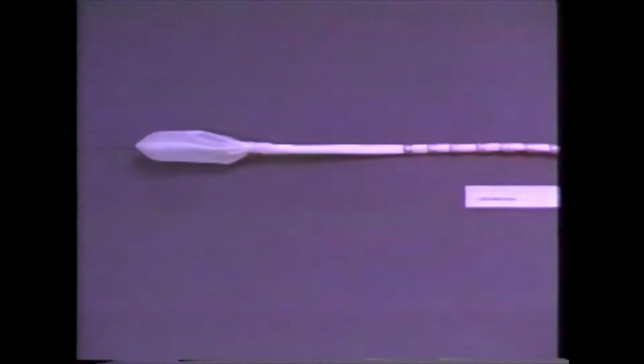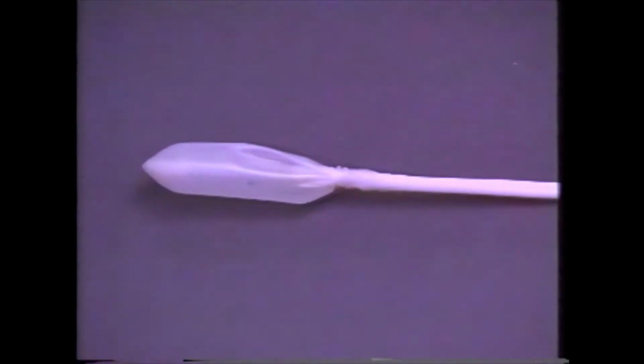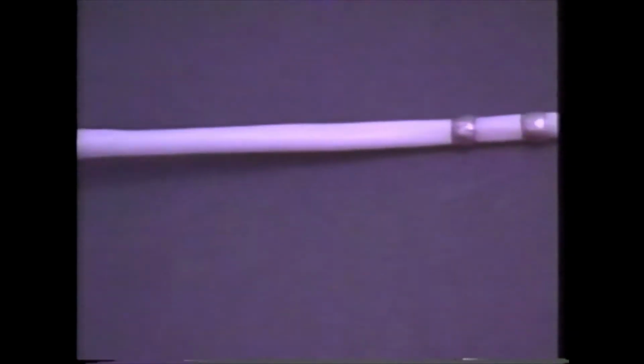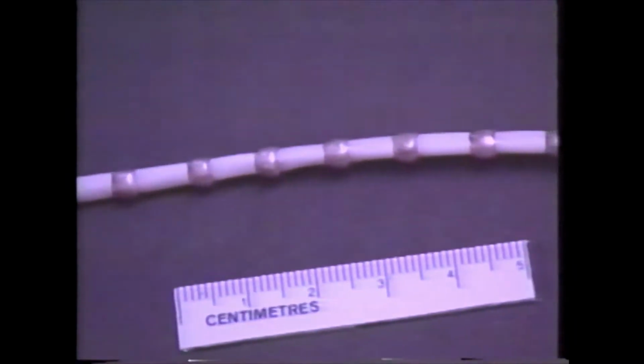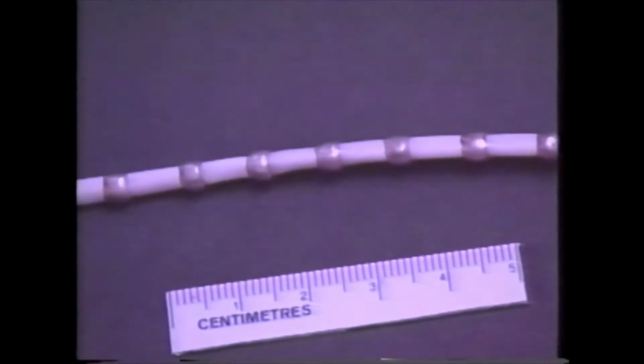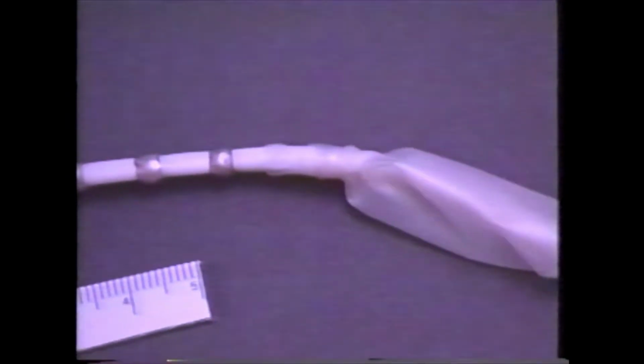An esophageal catheter was designed in order to measure the EMG of the diaphragm and esophageal and gastric pressures simultaneously. The catheter is made of silicone tubing for patient comfort and is shielded in order to avoid electrical disturbances in the EMG signal. At the distal end of the catheter, a latex balloon is mounted for gastric pressure measurements. Proximal to the gastric balloon, 9 rings are arranged 10 millimeters apart to form an array of 8 consecutive bipolar EMG electrode pairs. Esophageal pressure is obtained by a second latex balloon positioned proximally to the EMG array.